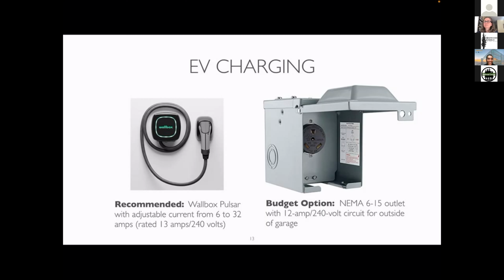So many people buying an EV will be offered an EV charger that's like a 50 amp charger. On a 100 amp panel, that's half your panel. We'd like to avoid that — it's not good for the grid, it's not good for your panel sizing, and you really don't need it. I have a 240 volt, 15 amp car charger, and that provides 100 miles of charge per night for my Tesla Model 3. So this idea that we all need 40 or 50 amp car chargers isn't true — we don't even need 30 amp chargers. Most of us need a 15 or 20 amp car charger, and that's plenty. I just wanted to put that out there.